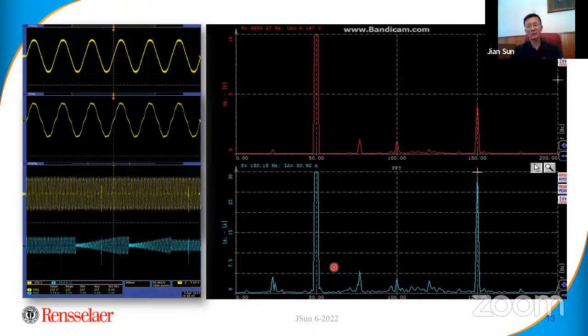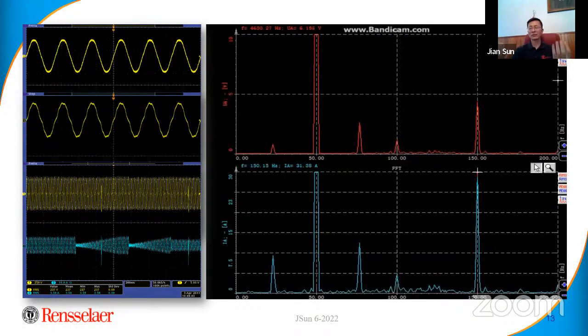The big bar in the middle is the fundamental voltage and current, 50 hertz. Next to it, on both sides, you see two small harmonics. They have the same distance from the fundamental, so they're symmetrical. Right now they're small at the beginning, but this is a live recording, so you will see these two harmonics start to move, grow, and eventually grow to a level where the system shuts down and the recording stops.